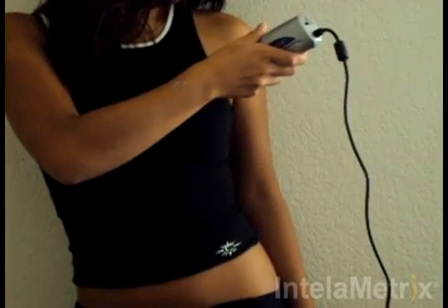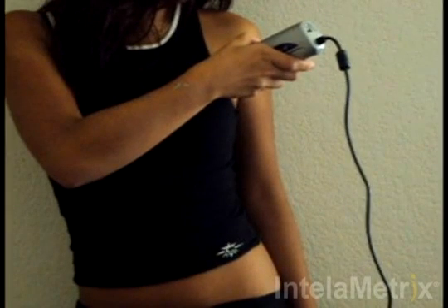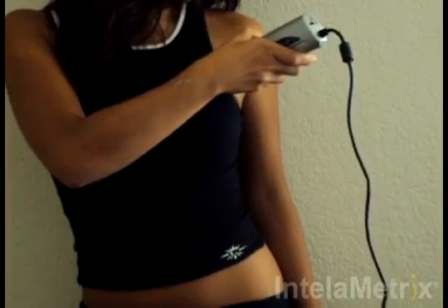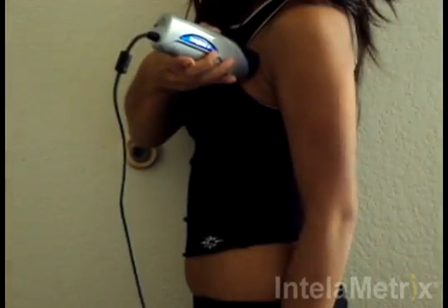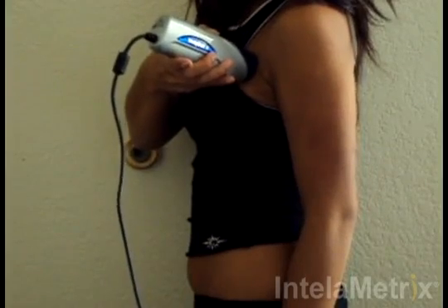After the gel has been applied, you are ready to take the measurement. Move the device to the measurement site. Hold down the button while moving the device up approximately one quarter to one half an inch, and then down through the measurement site and about a quarter to half an inch below. Move the device up and down at a comfortable speed for three to four seconds. Make sure you maintain contact with the skin the entire time, keeping it perpendicular to the surface.